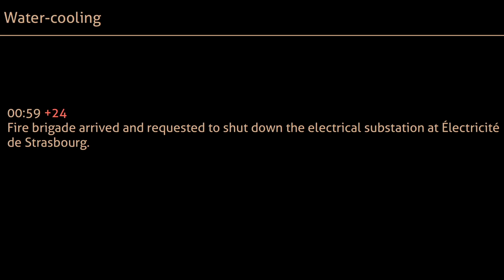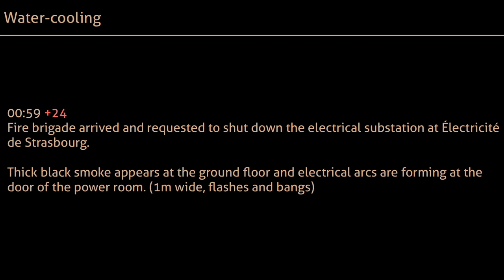The fire brigade arrives, and they requested to shut down the electricity at Electricité de Strasbourg, basically the one maintaining the power lines. Thick black smoke appears at the ground floor, and electrical arcs are forming at the door of the power room. You have 1 meter wide flashes and very, very loud disorienting bangs. And they deployed our water lines while waiting for the substation to be powered off.